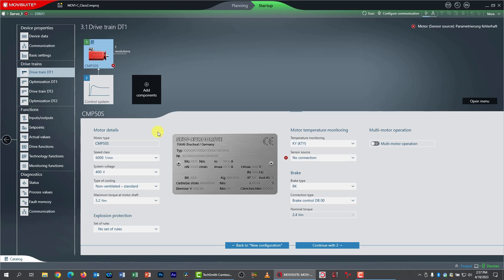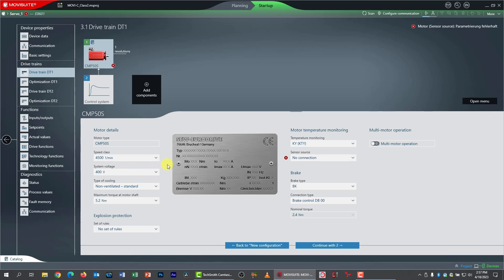First of all, I need to be sure that I have the right motor speed class. Servos come in different speed classes with system voltages. This information is on the nameplate. My motor is actually a 4500 RPM speed class. 400 volts is fine. That is not the line voltage, that is the motor voltage. So I'm going to leave that alone.